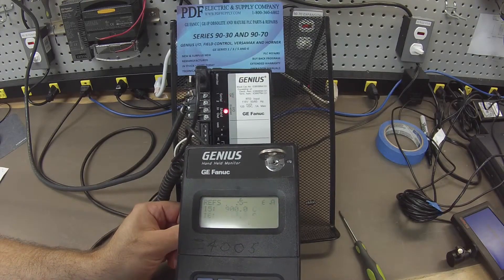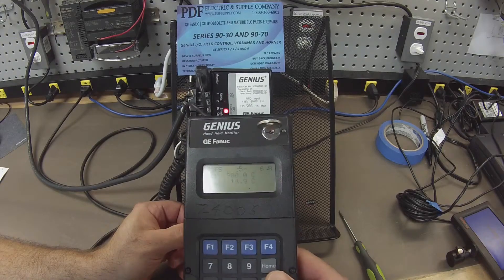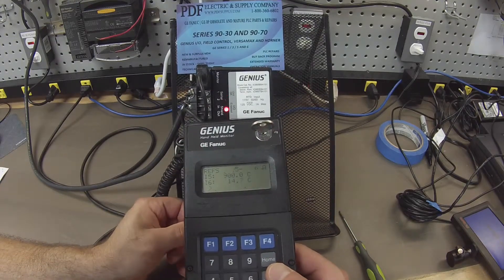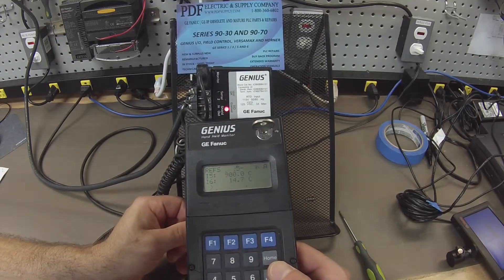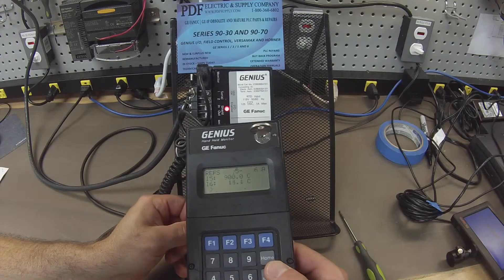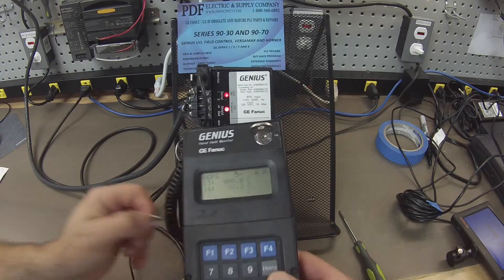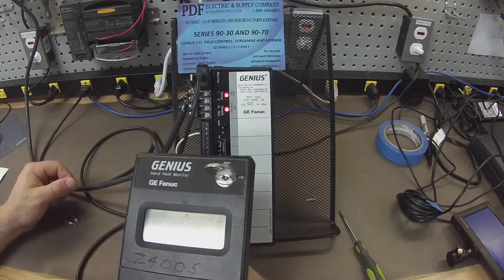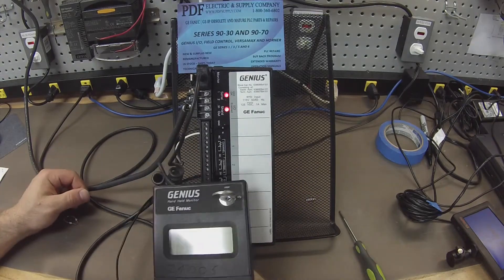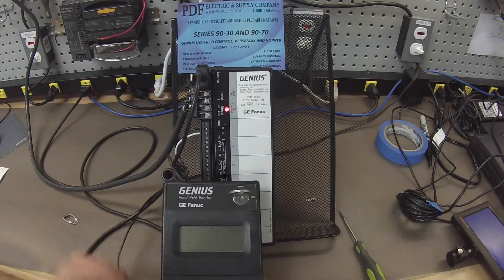I'm probing terminals 29 and 30. 29 and 30. It's difficult to keep it on here. But they're all within the 15 degrees Celsius range, which is good that we see all the channels are the same.